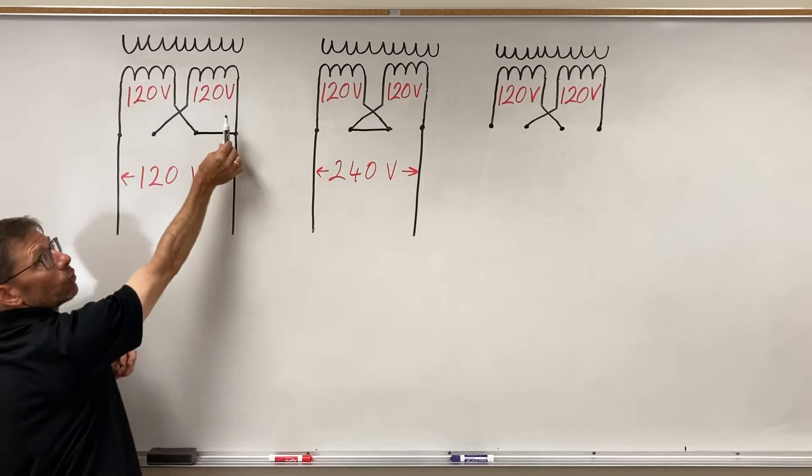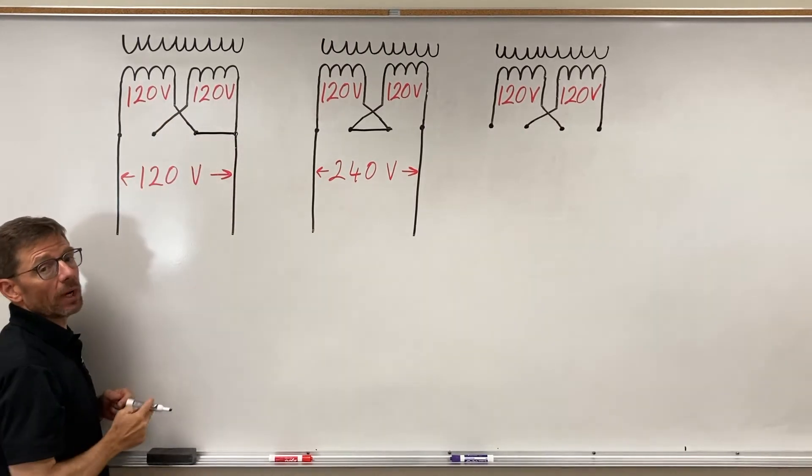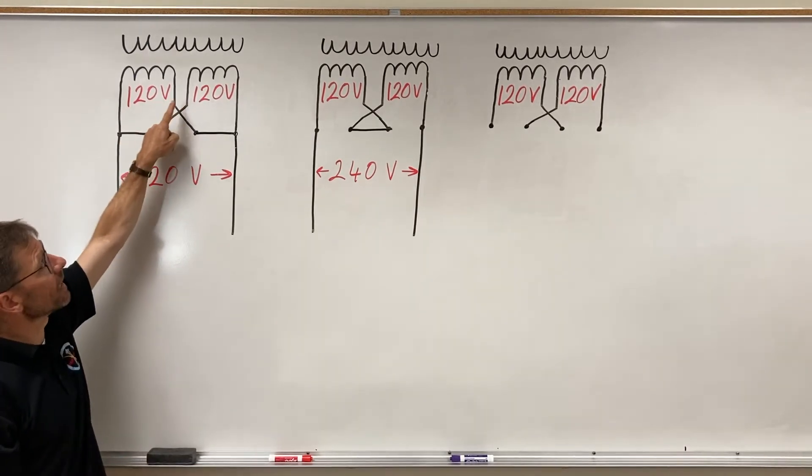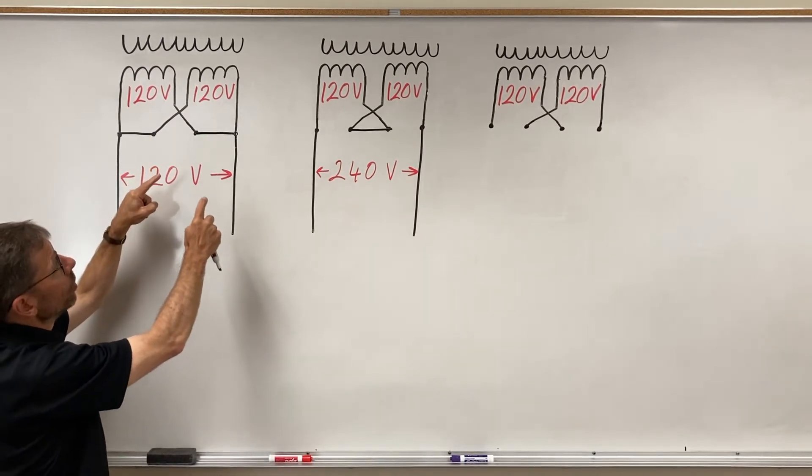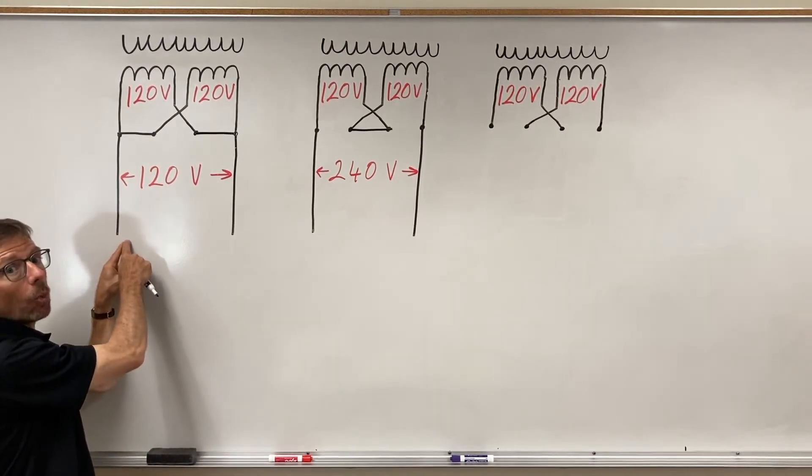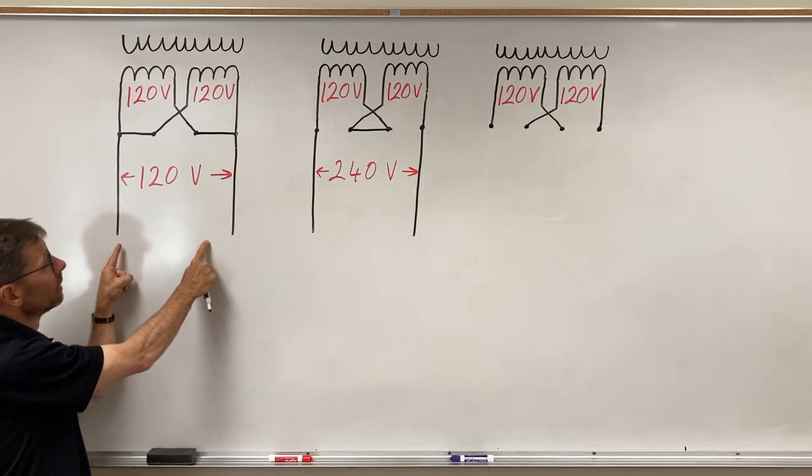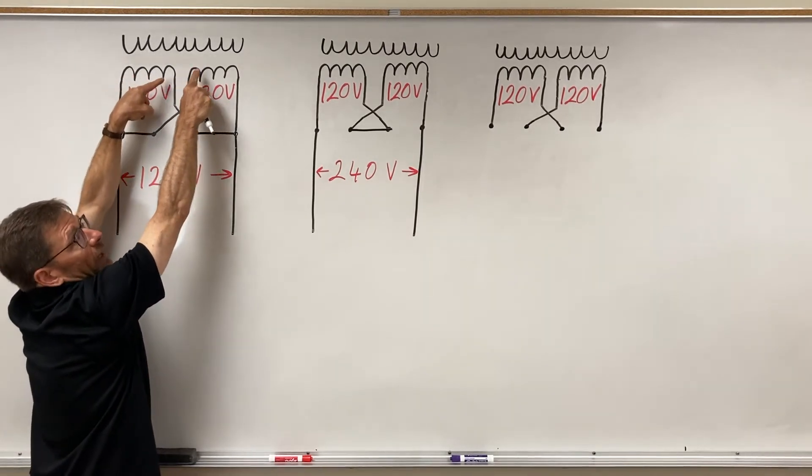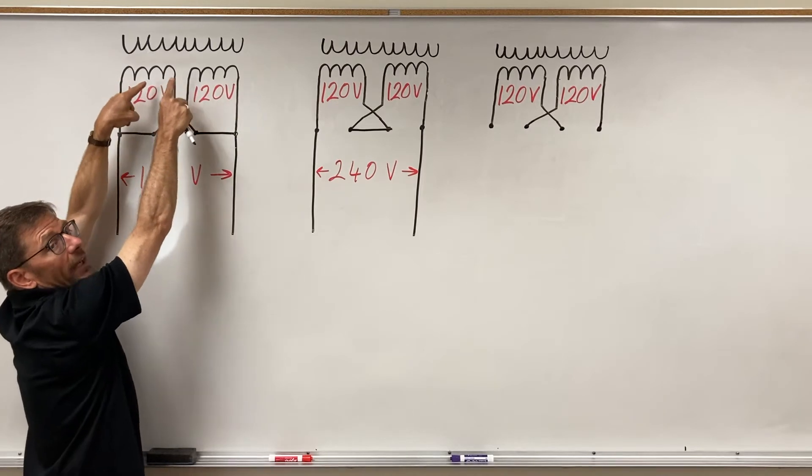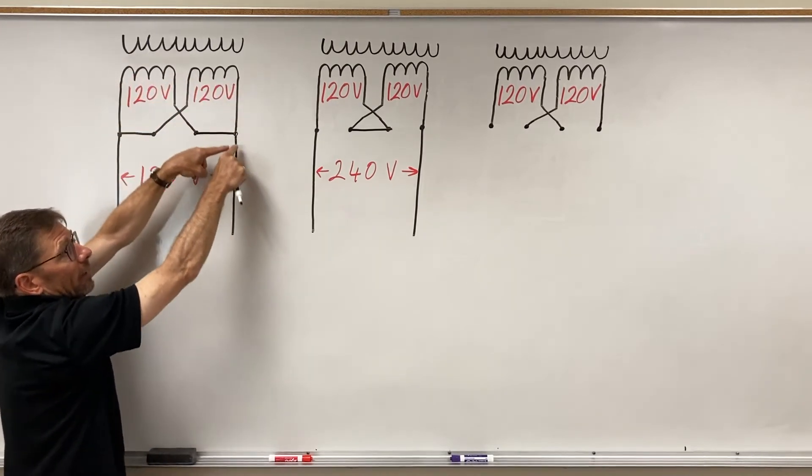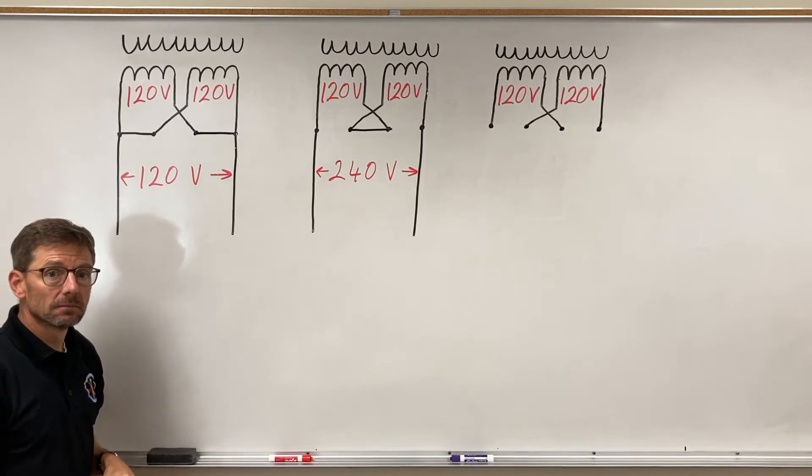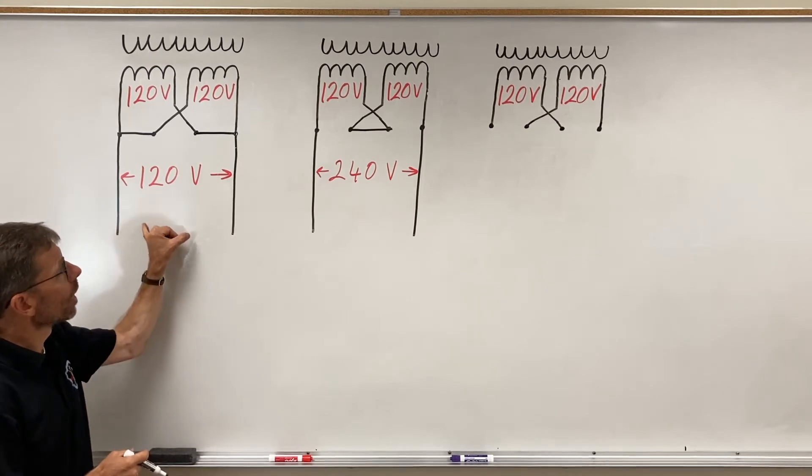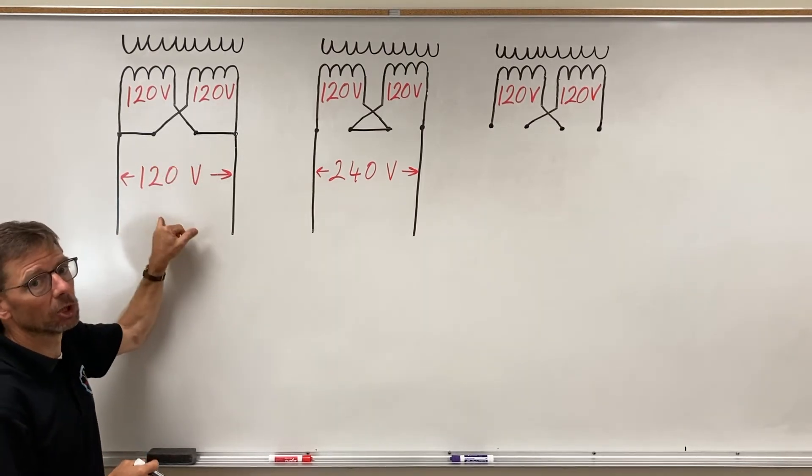That jumper connects the right side of this winding and the right side of this winding. And if I put the other jumper here, it connects the left side of this winding and the left side of this. So if I go from this line to see what is my voltage potential across here, I will go up here, splits off, develop 120 volts on each winding in parallel, and then come to this other line. 120 volts parallel, lower voltage option.